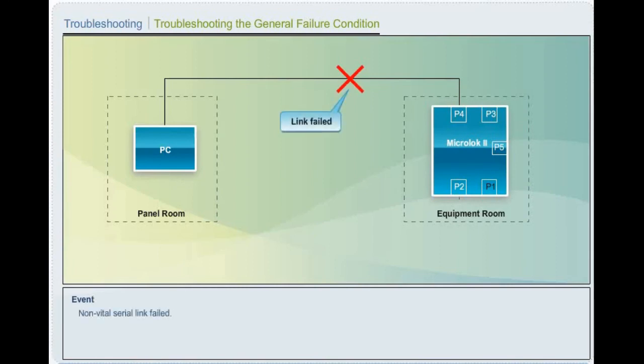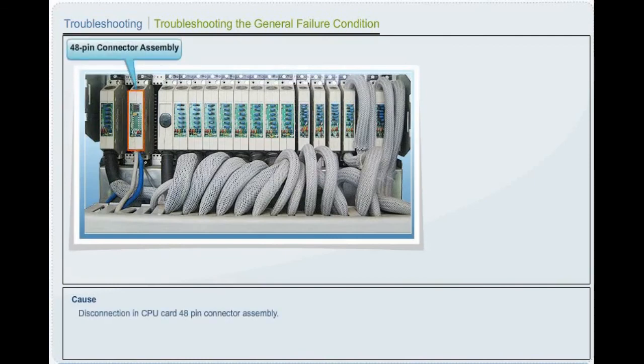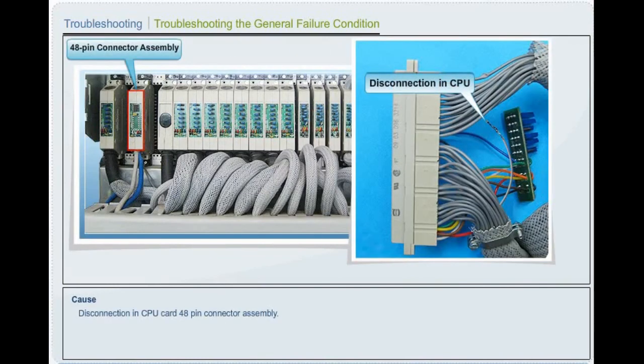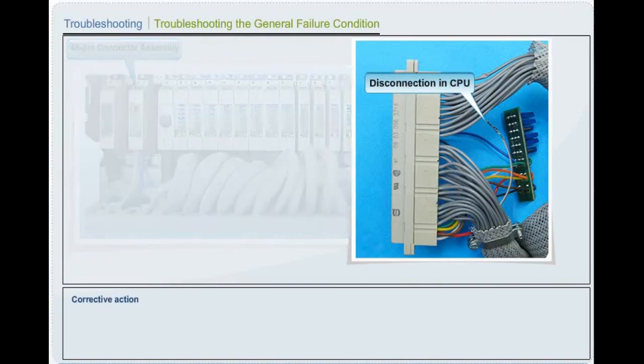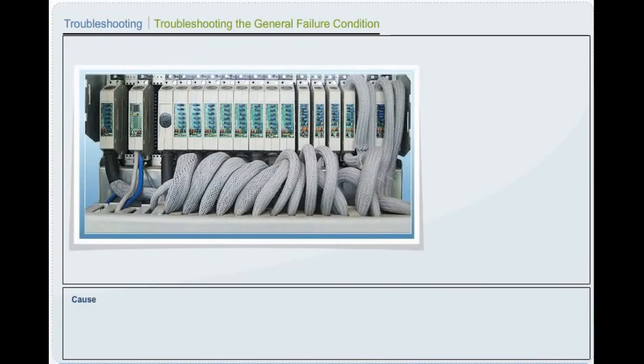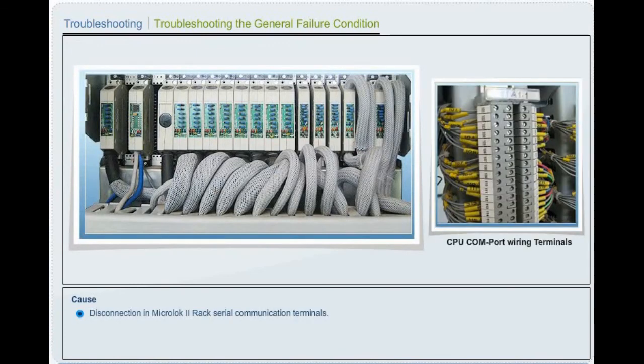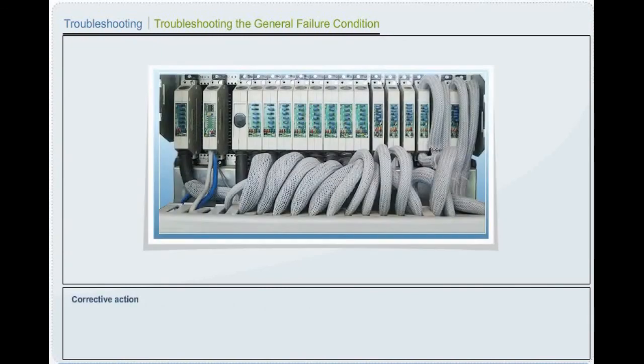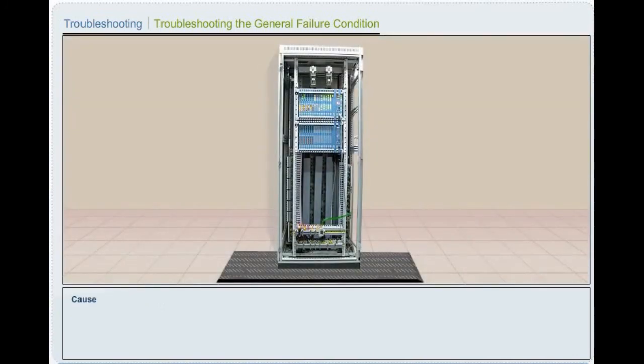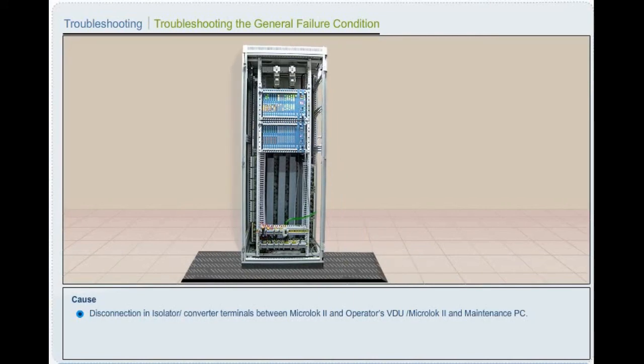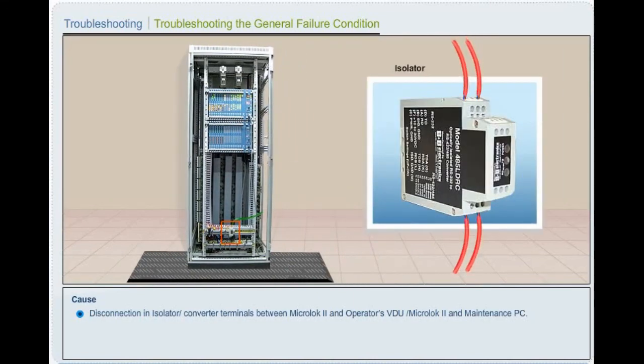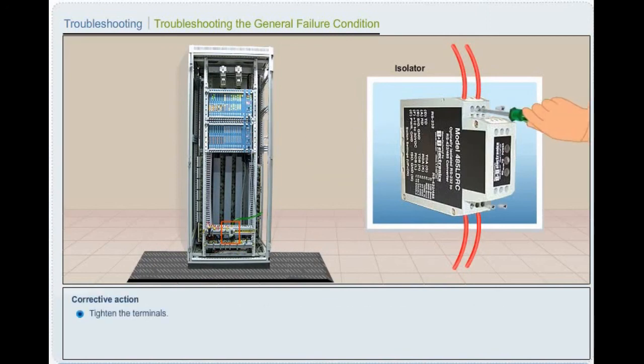Non-vital serial link failed. Cause: disconnection in central processing unit card 48-pin connector assembly. Ensure all the crimps are locked. Cause: disconnection in Microlok II rack serial communication terminals. Corrective action: Tighten the terminals. Cause: disconnection in isolator or converter terminals between Microlok II and operator's VDU, Microlok II and maintenance PC. Corrective action: Tighten the terminals.